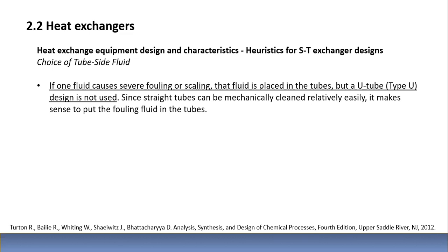Interesante que nos explica que cuando un fluido, como es una solución orgánica, no puede ser una solución diluida o concentrada de jugo de maracuyá, de café soluble, en un intercambiador, cuando los tubos están rectos y van de lado a lado, es fácil limpiarlo. Pero si el intercambiador tiene una vuelta en U, tiene tubos que dan vuelta en U interiormente, esa vuelta en U es muy difícil de limpiar. Entonces, si es un fluido que tiene un severo problema de ensuciamiento, produce ensuciamiento, el tipo de intercambiador U-tube no es el más recomendado.